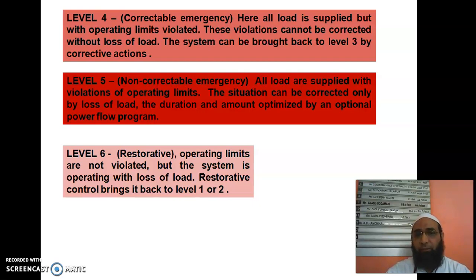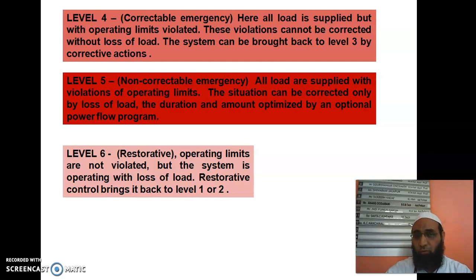Level 5 is the non-correctable emergency. All loads are supplied with violations of operating limits. The situation can be corrected only by loss of load, with the duration and amount optimized by an optimal power flow program.